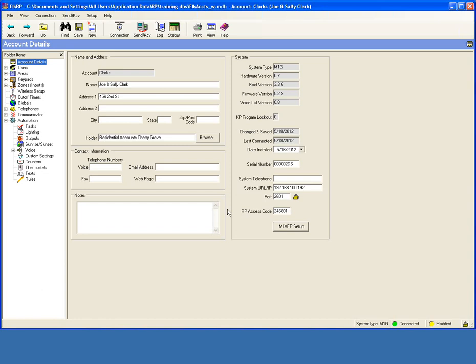How many temperature sensors can you have? For example, outside temperature for an attic fan, crawl space temperature for a crawl space heater. The system supports up to 16 temperature sensors. And the reason that there's a limit on that is because the zone temperature sensors, the M1ZTS and the M1ZTSR, can only be connected to the main board.